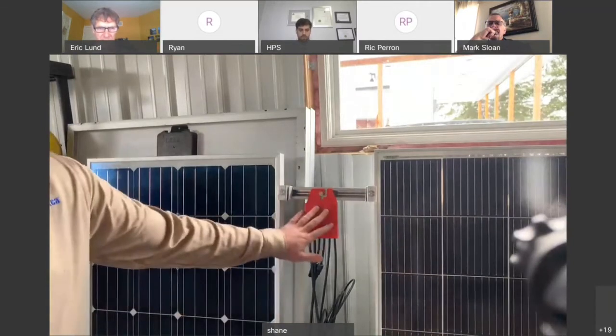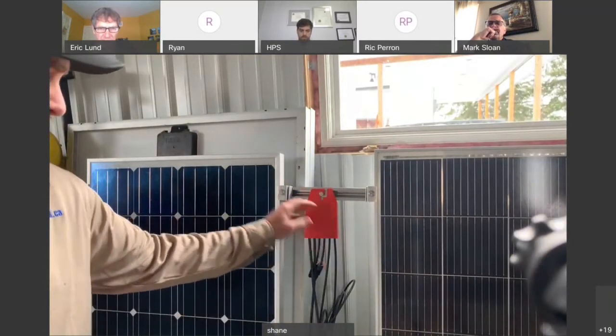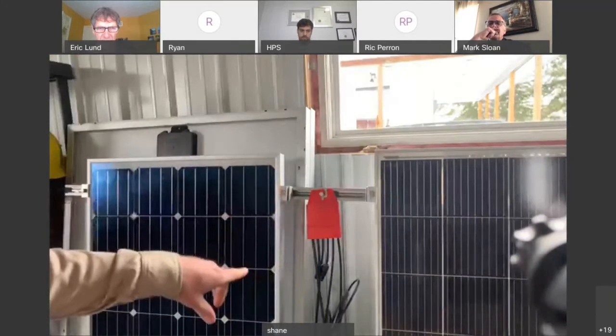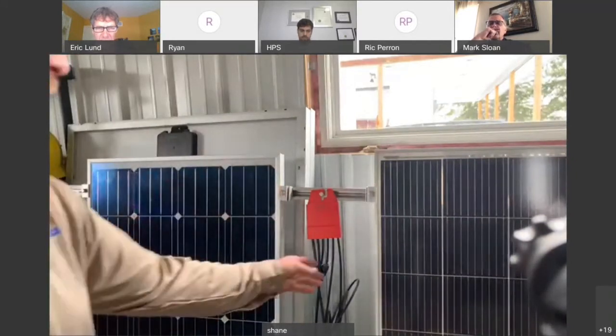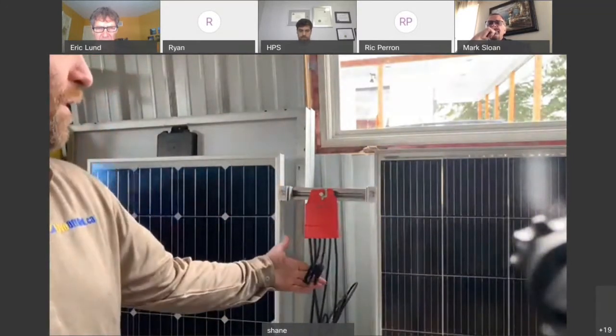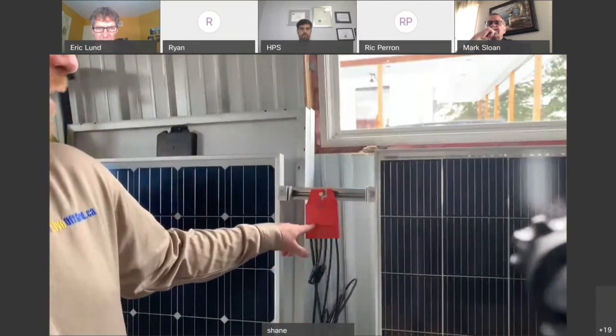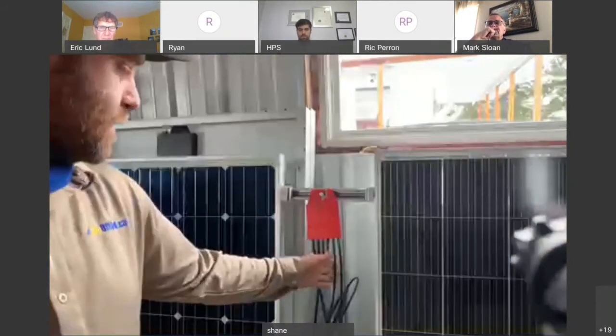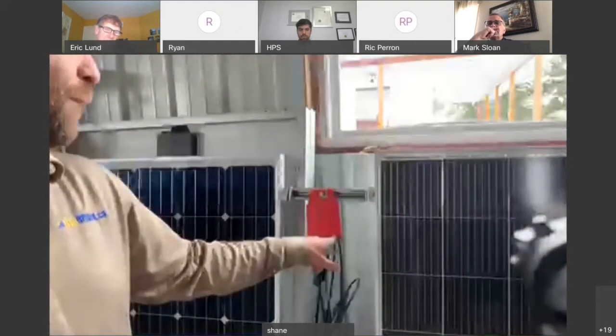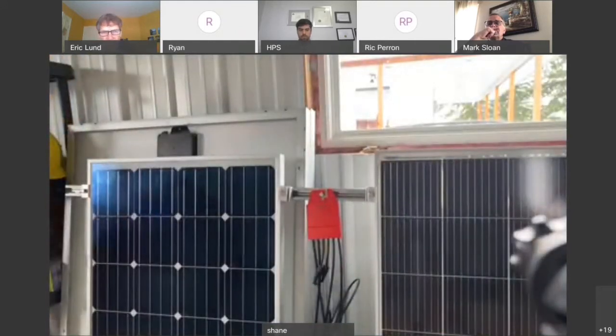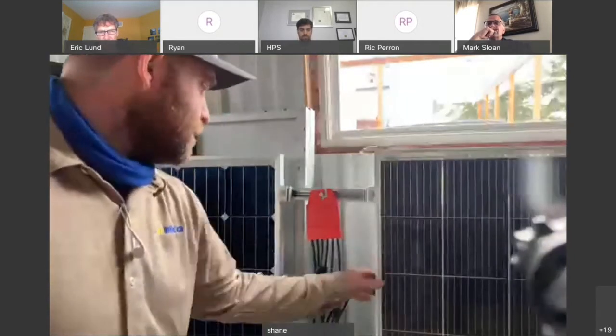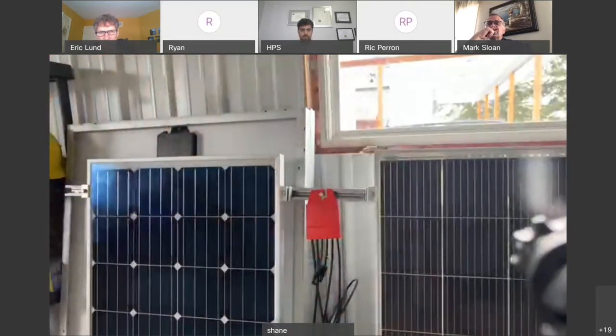So this is our rapid shutdown module. Usually you're going to have 2 modules in series, and you bring them into here. There's a small micro switch in here that operates on a 24-volt input. That 24-volt input is fed from an initiator, which we'll go over after, and it tells these things to stay in a closed state. Then we feed this into our 2 panels and move on. So we'll have one of these for every 2 panels.